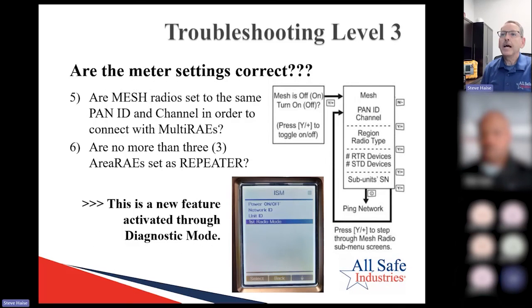And then finally, for troubleshooting level 3, we want to confirm that if you're going to connect portable instruments to your system as well, so not just AreaRAEs going back to the host radio connected to your laptop, but maybe you want to bring MultiRAEs into the fold as well, then you'll need to ensure that the mesh radios are set the same. So you'll go to the mesh radio menu on both your multi-ray and your AreaRAE, and you'll confirm that they're communicating on the same PAN ID. PAN stands for Personal Area Network, and this is how you can connect MultiRAEs to your AreaRAEs, and then the AreaRAEs can transmit all that data back to your host computer.